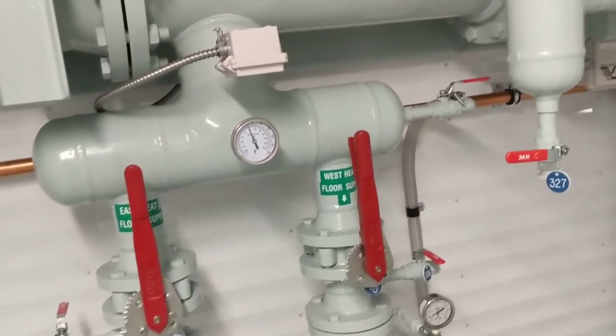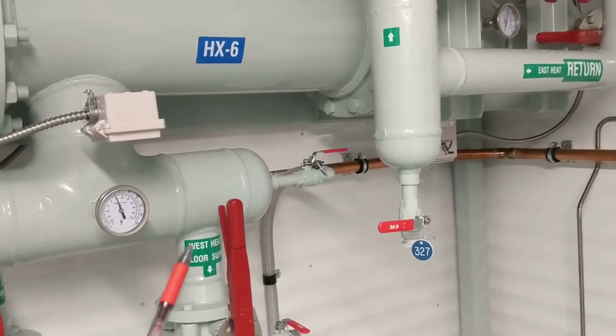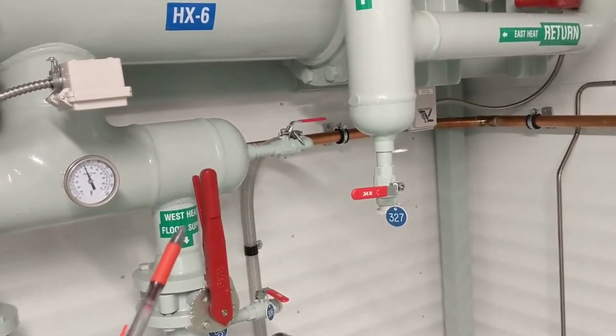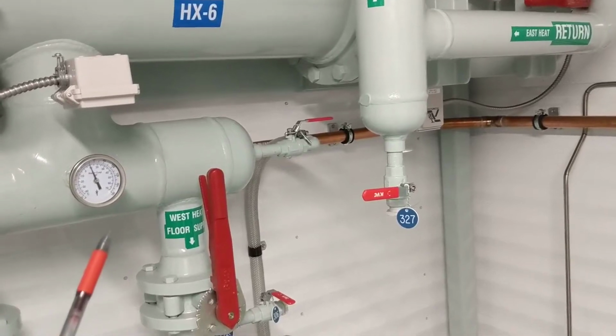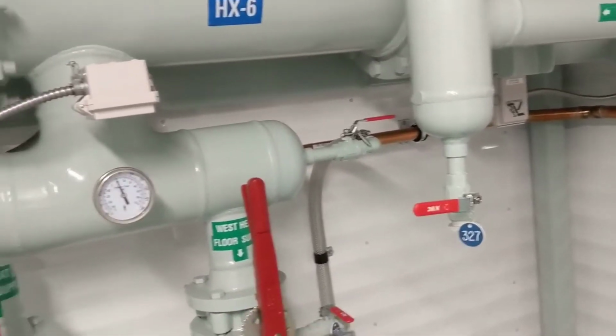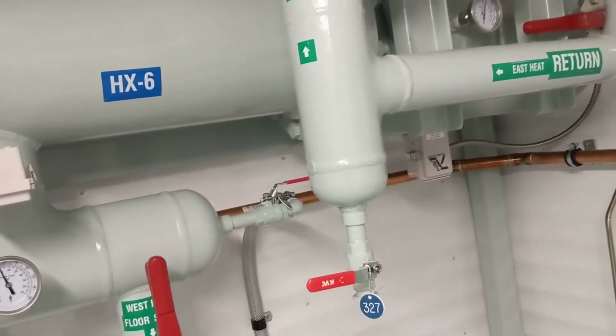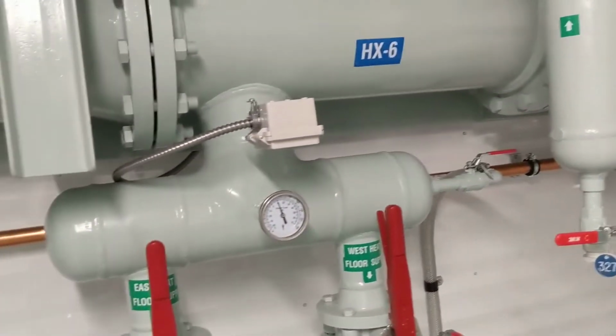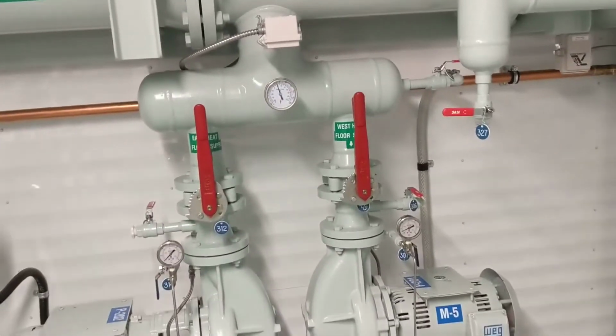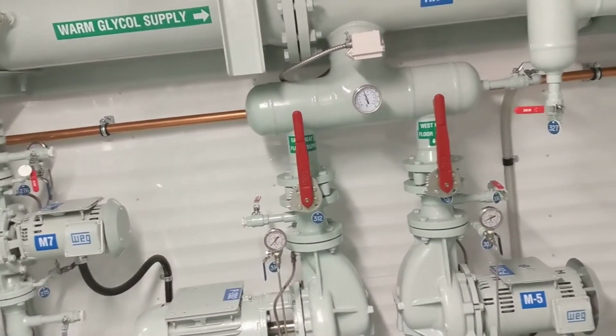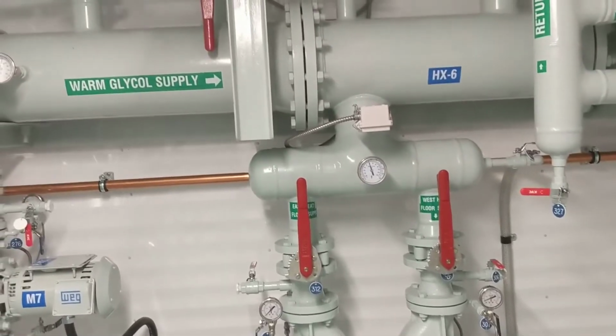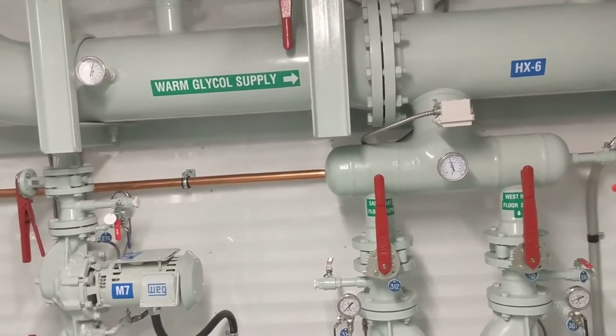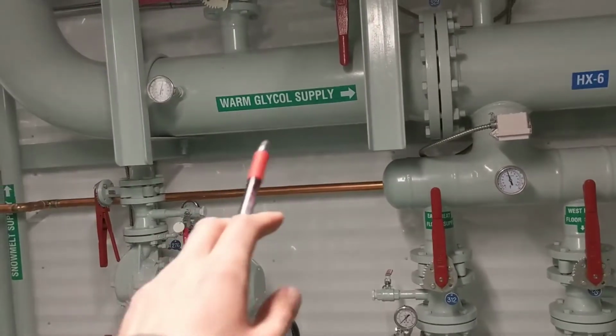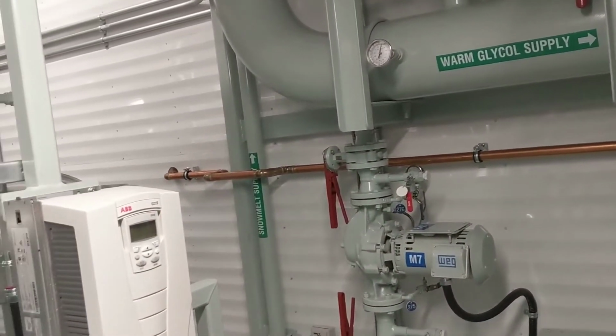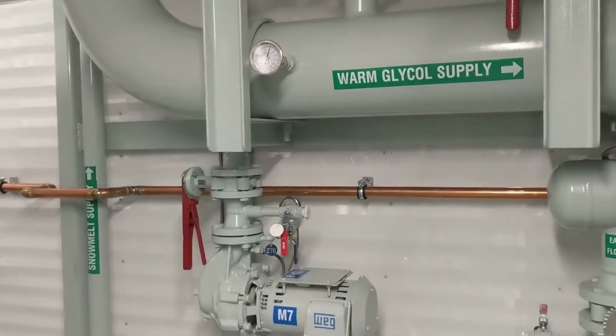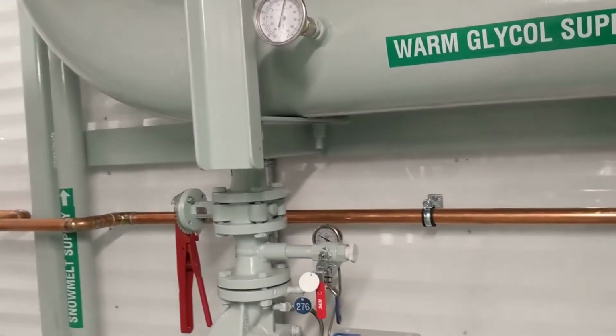It goes out there, it gives up its heat to the space around it, essentially, and it comes back and completes that loop, coming back cooler than what it went out at. So it's taking some of the heat off the glycol, and so that glycol, you'll remember, is warm because it got its heat as it was condensing the ammonia.